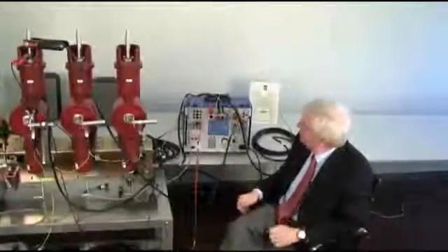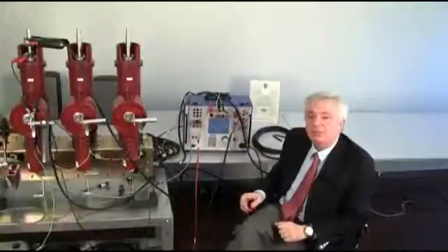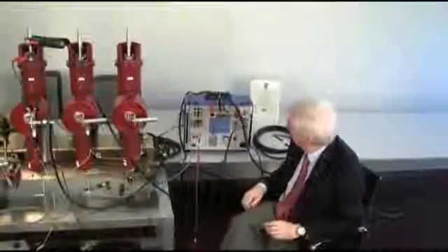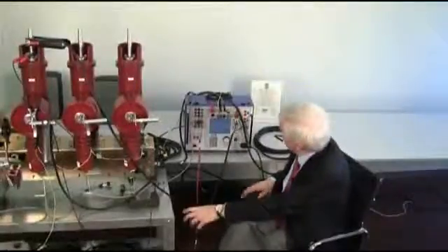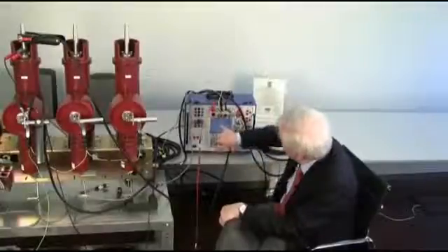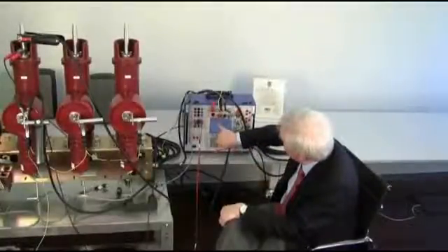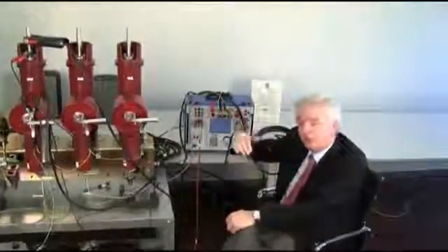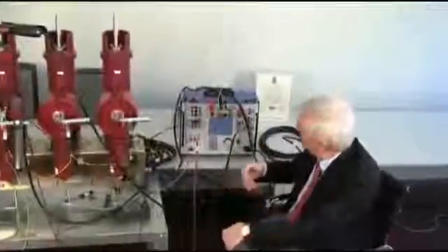Now, I will repeat the same test as before, but during the open instead of close. During the open, of course, the contact is open. By the way, excuse me, I have changed the setting to 100 amps and 10 milliohm so that we can better measure the resistance variation along the curve.